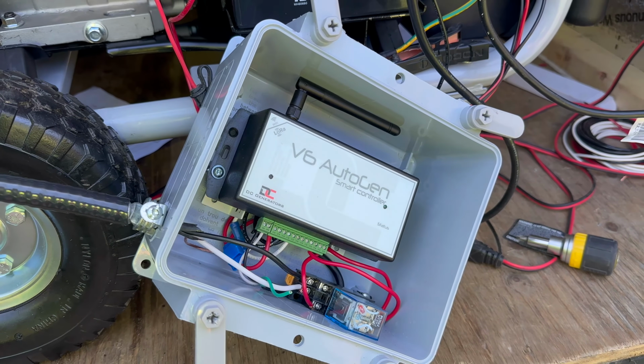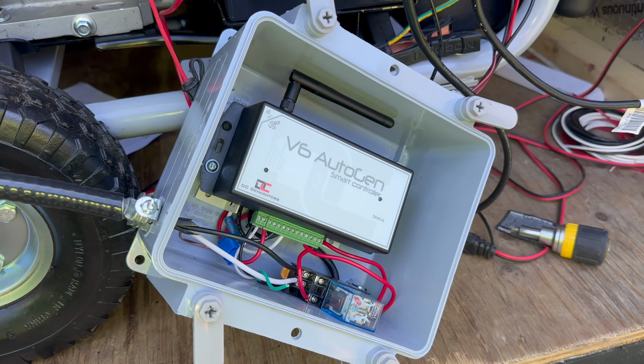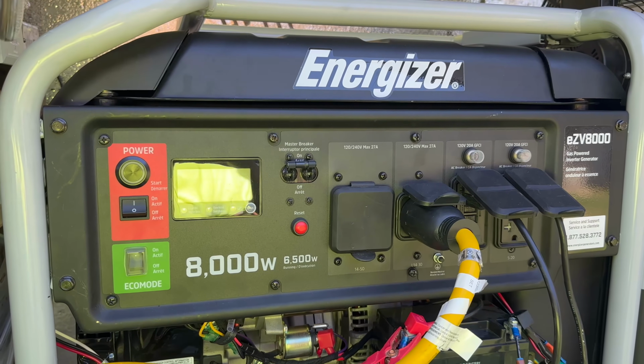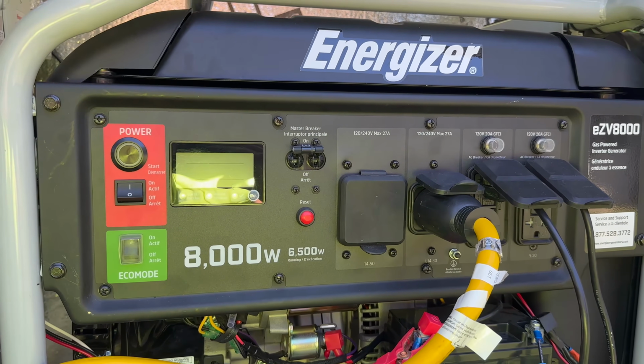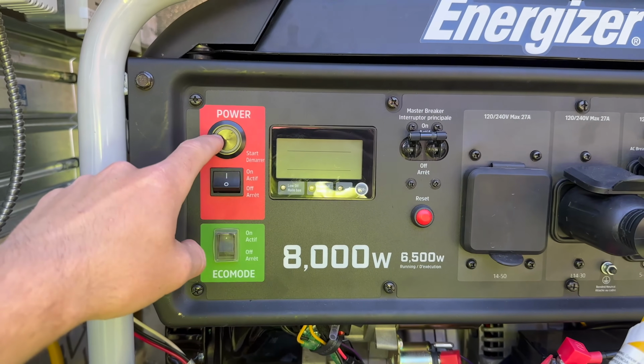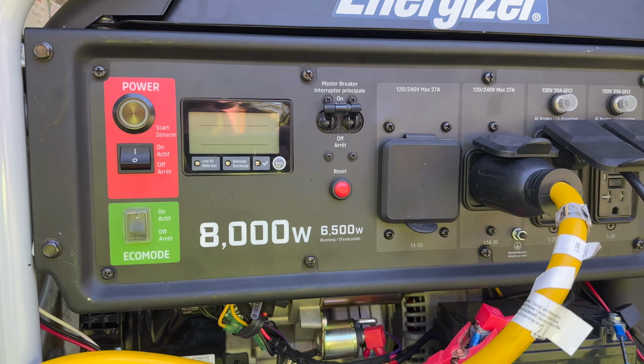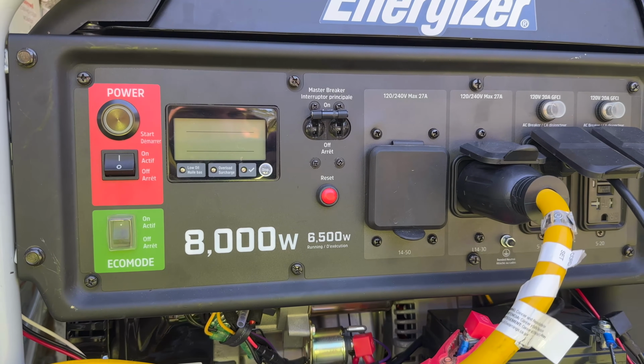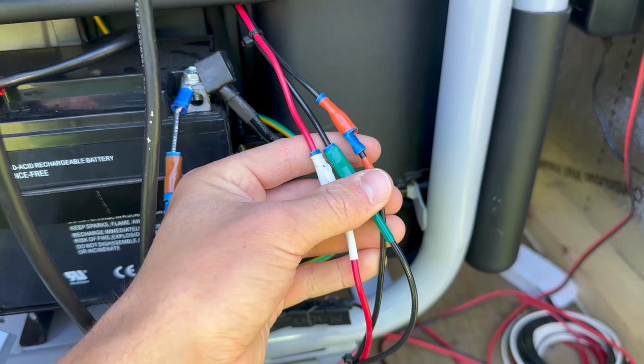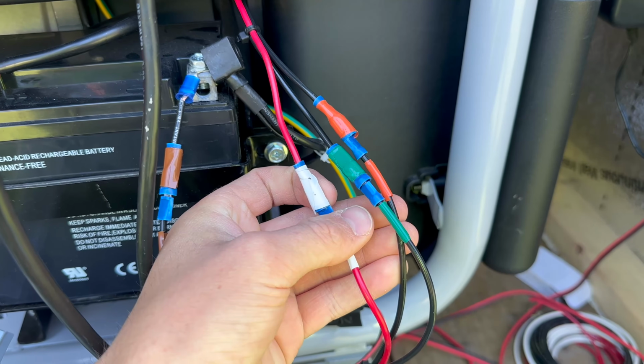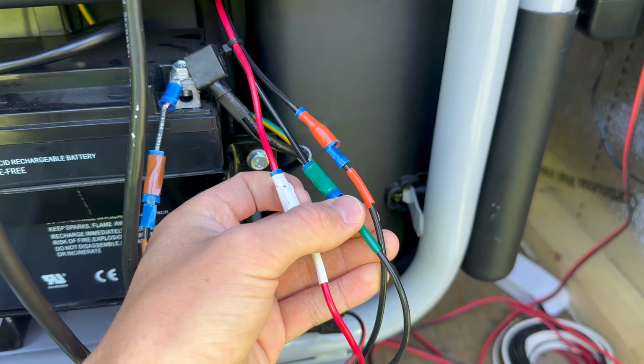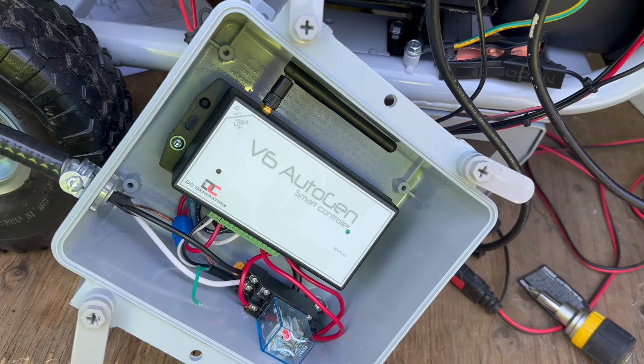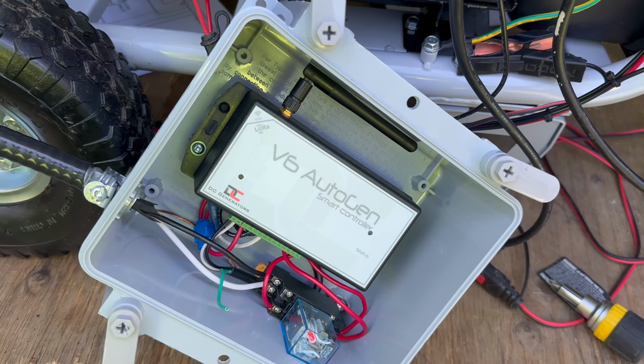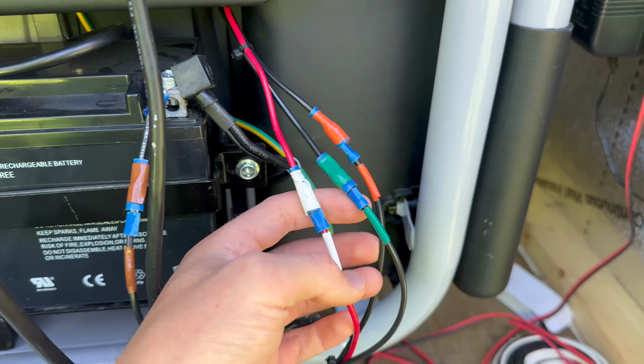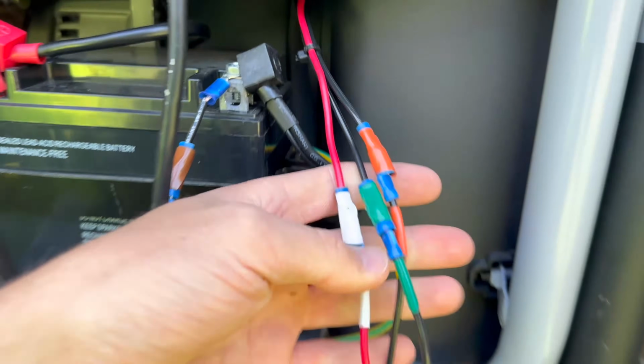The way this module starts the generator is with a few different electrical connections. When I installed this, I had to install some relays behind this cover, which tie into the start switch and the stop switch. I have two automotive type relays installed behind there, which are tied into these three wires. These are what control those relays. We have a common positive and two negatives, which get grounded out when this runs the sequence that determines they need to be switched on or off for those relays. So just three connections from the relays inside of the generator.